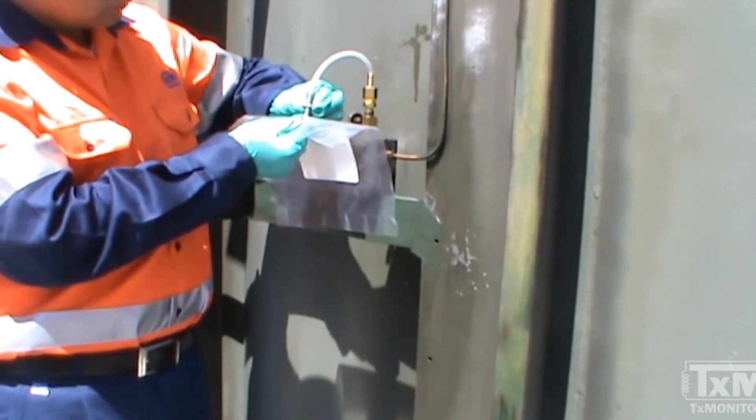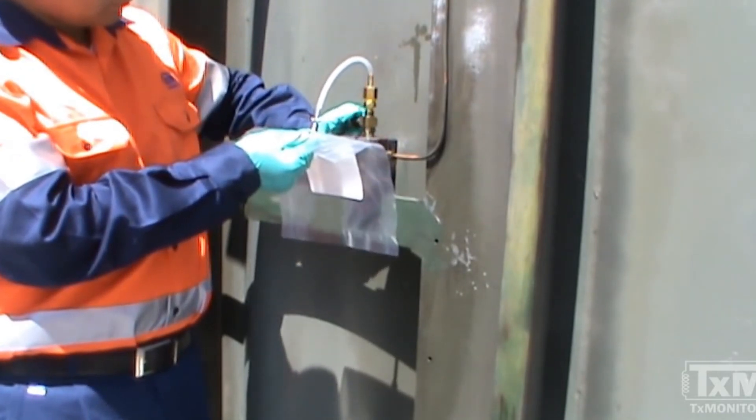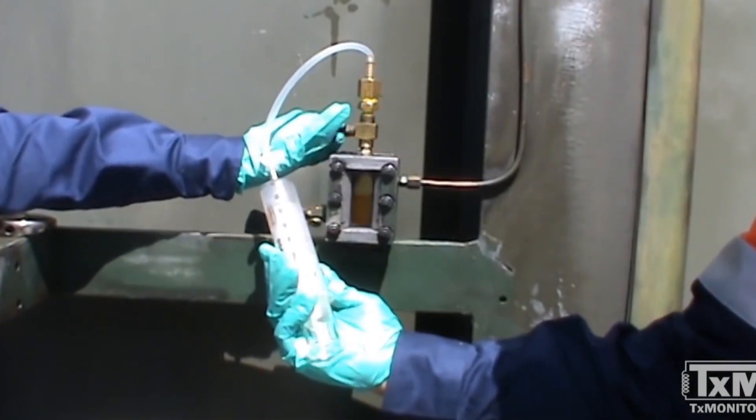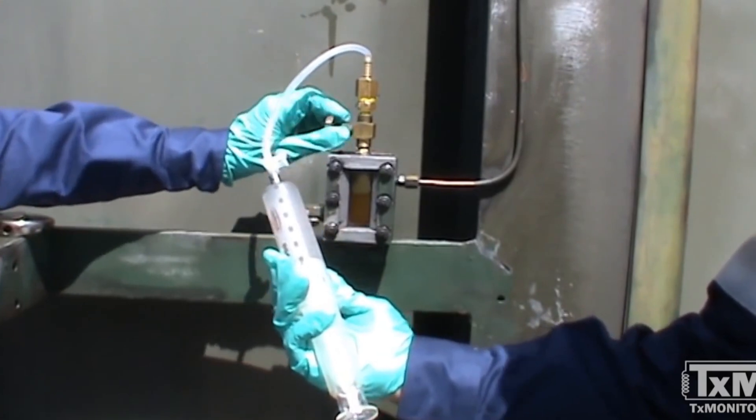Open the valve on the sampling container, and then open the top port of the sampling device to allow the gas to flow. You will notice that the oil level will start to rise again as the gas is pushed out of the sampling device.